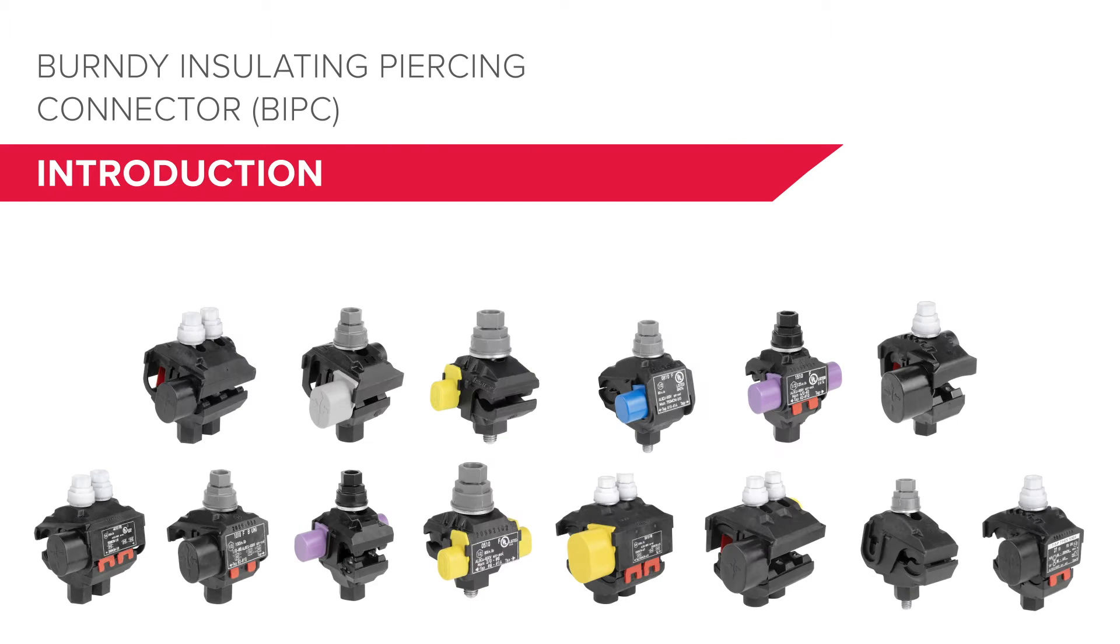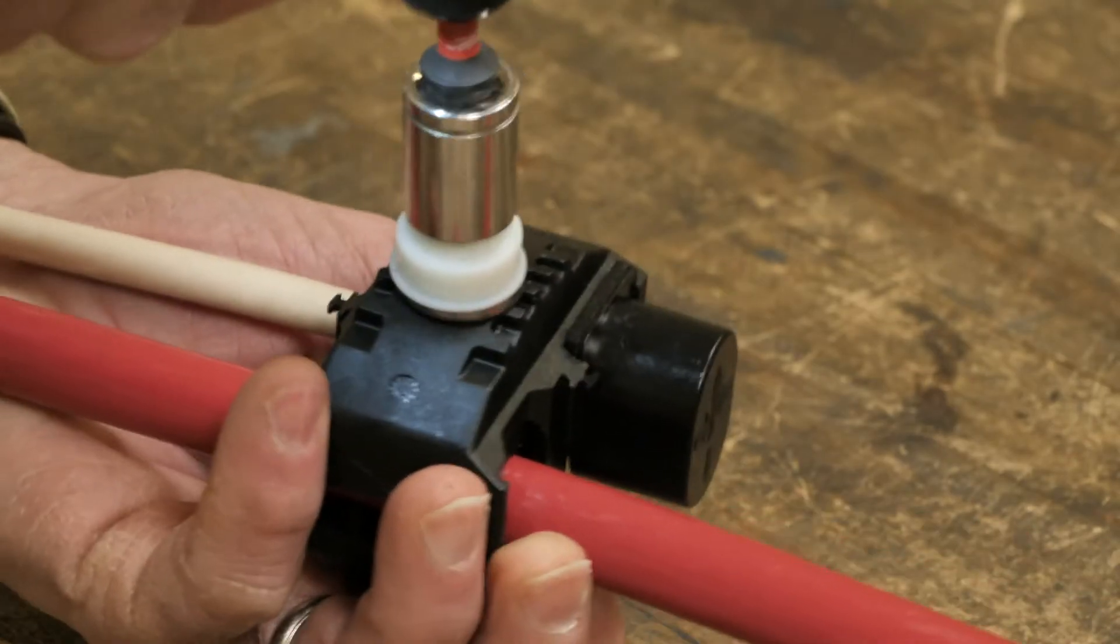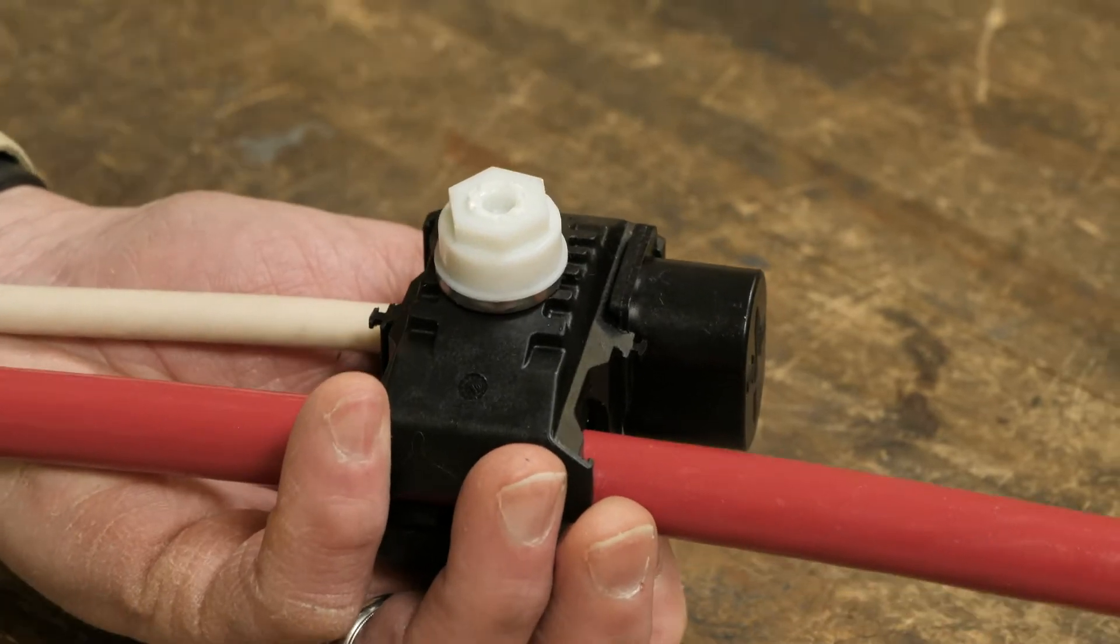The wire range has been expanded to accommodate a run from number 8 AWG to 750 kc mil and a tap from number 14 AWG to 500 kc mil. A simple wrench or impact driver with appropriately sized socket is all that is required to install these tapping and splicing connectors.